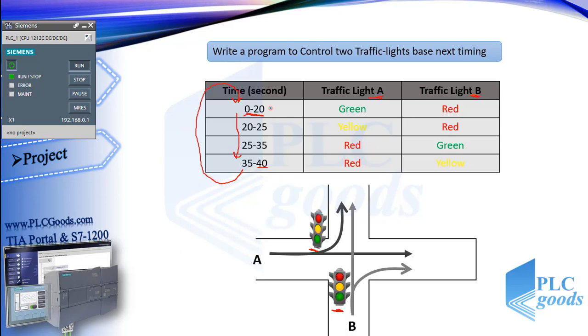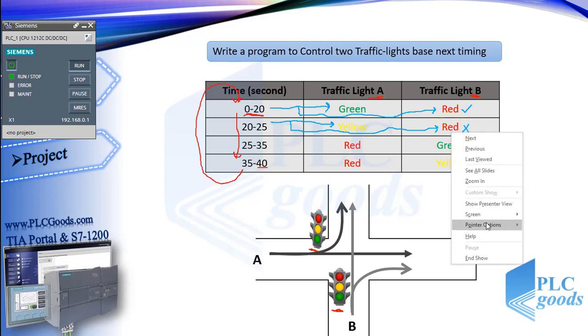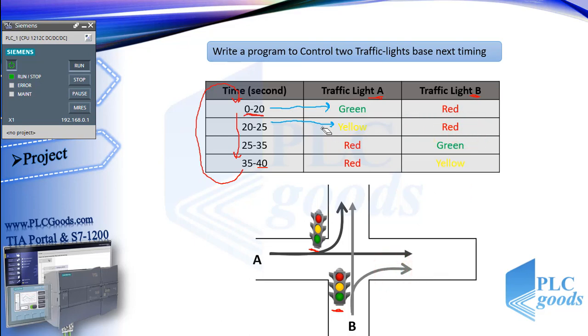Let me explain the first way. The first condition turns on green A, and it also turns on red B, so I can make a branch to turn red B on. But this approach is not correct in PLC programming. Why? The second condition turns on yellow A and red B. Now suppose the timer is at 10 seconds — based on the first condition, red B must be on, but the CPU turns it off because of the second condition. In other words, the second condition takes priority over the first. This program must be written based on outputs: I must use one output for each light and find what conditions turn them on.